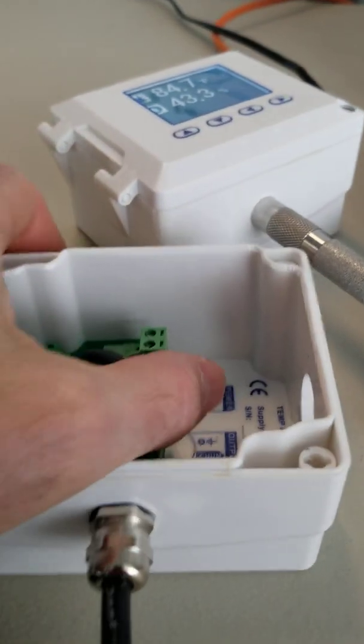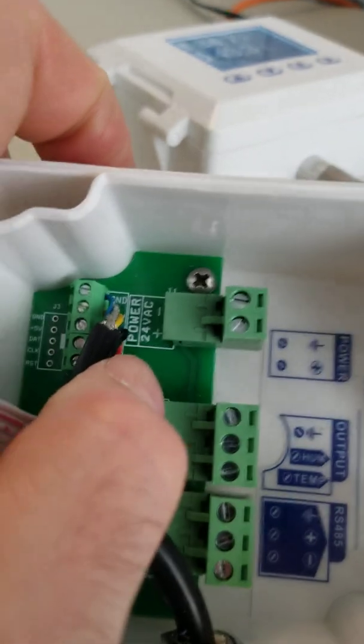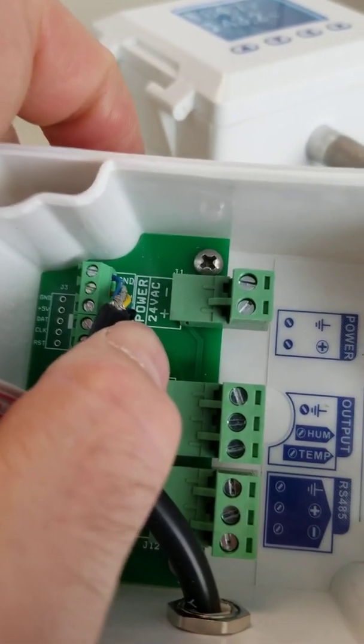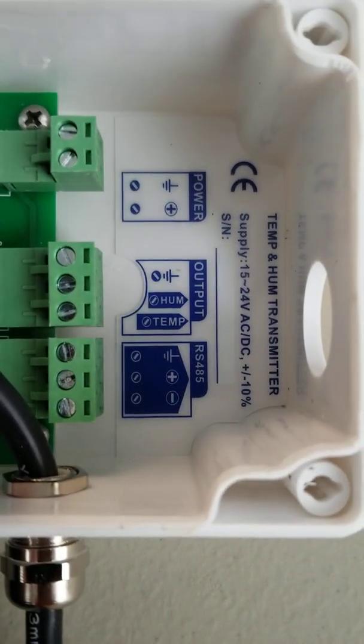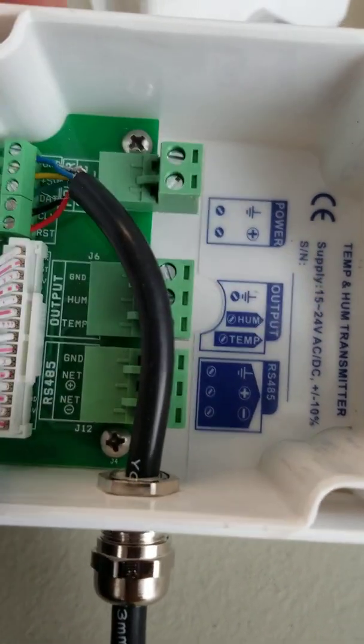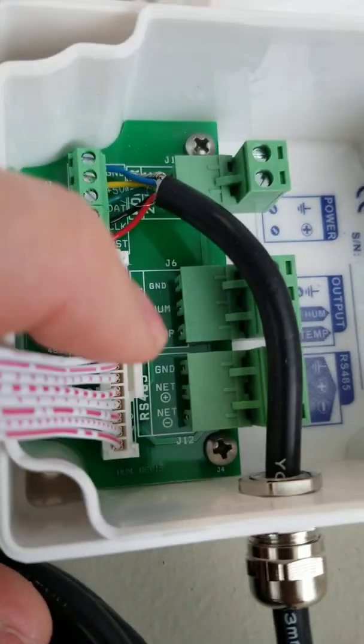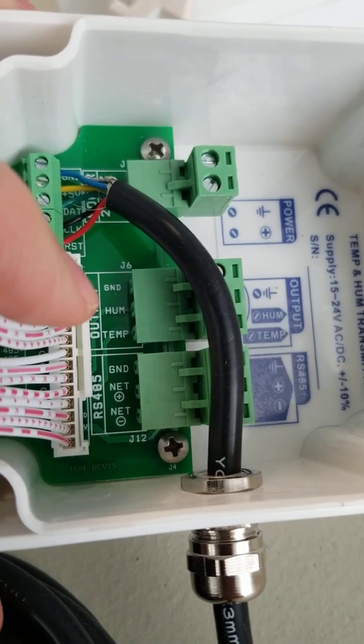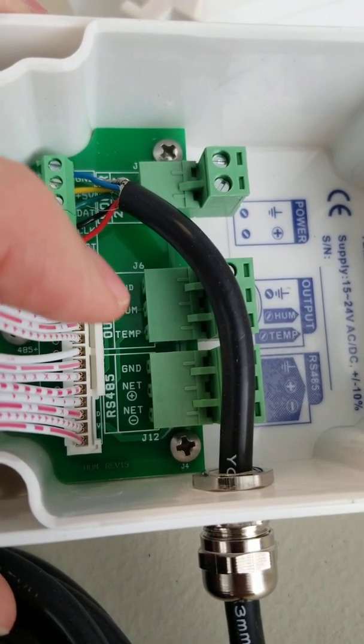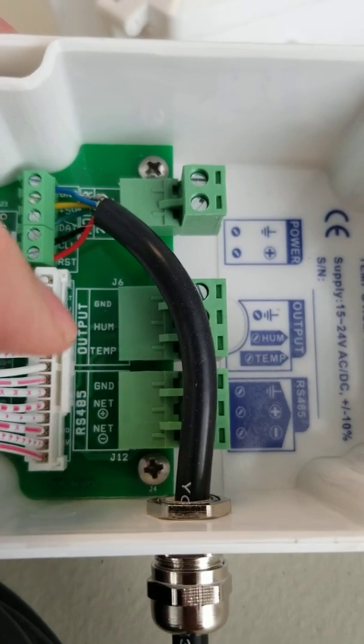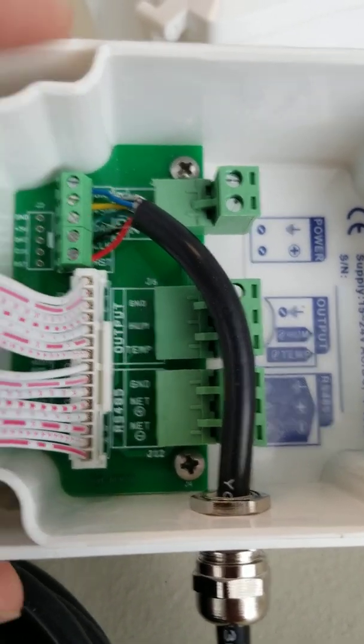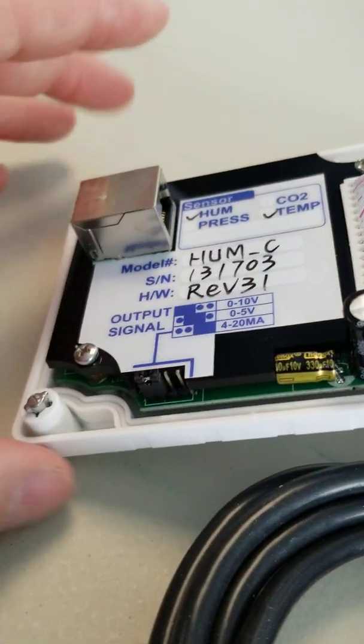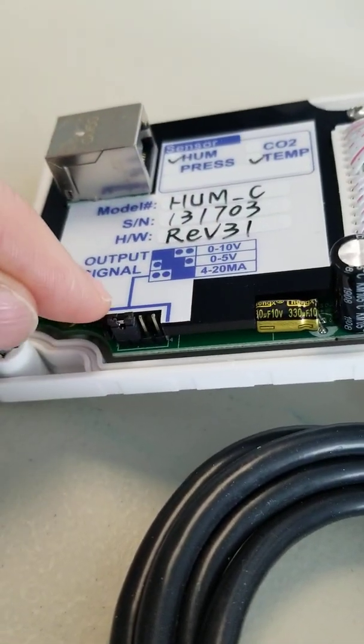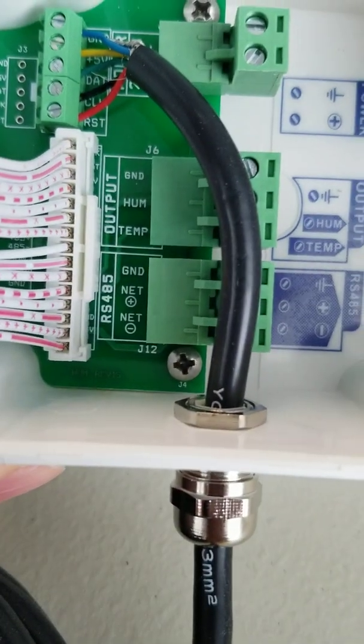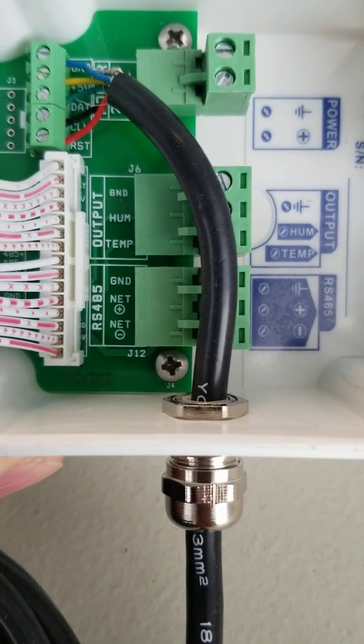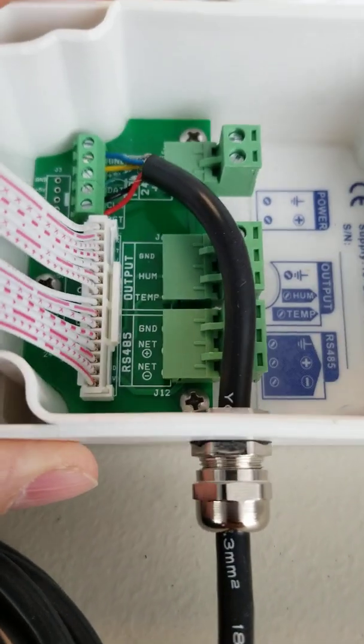Here's where the connections are made inside. I'll move this cable. There's the power connection at the top. Works actually with DC or AC. You can see that little note in the bottom there. This next one down, right here, those are the analog outputs, so your temperature output and your humidity output and the ground. And again, those will output different things based on what this jumper over here is set for. And then we've got at the bottom our Modbus RTU over RS485 connection, if you were to use that.